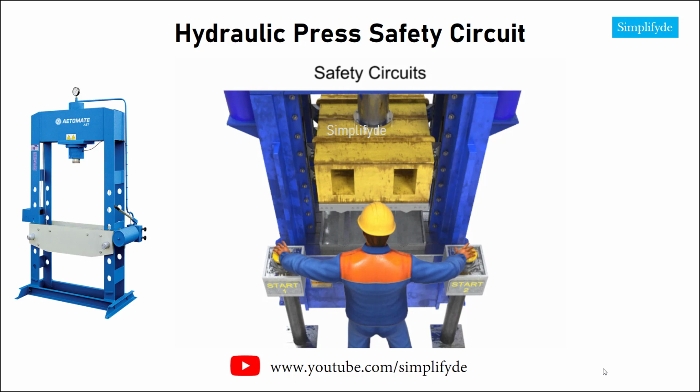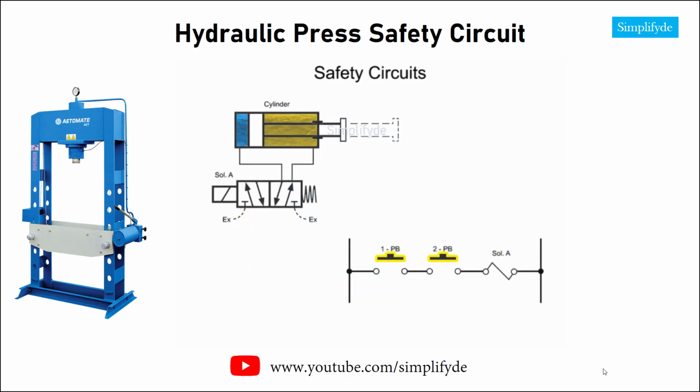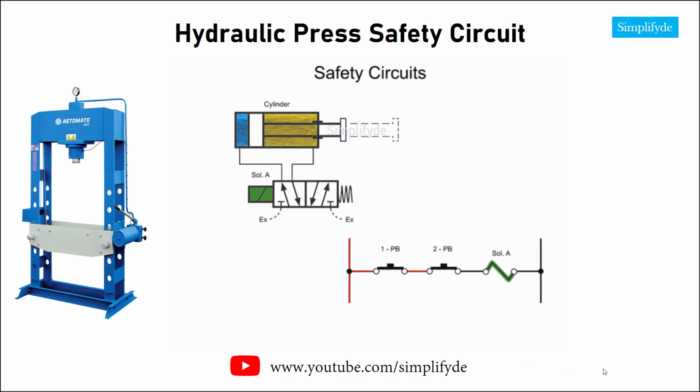Two-hand controls can also describe a machine that requires two separate operators, typically located on opposite sides of the machine. Both operators must be in place to allow the machine to start its cycle. For this type of machine, two-hand operation controls typically consist of two push buttons wired in series. This type of two-hand control is simple to install and is fairly safe if two operators are present with physically separate control panels. If only one button is depressed, the electrical connection is not made and the machine will not start. As shown in the circuit, only the actuation of both push buttons allows the solenoid to energize. The solenoid then shifts the valve to allow air into the cylinder, which produces the machine's stamping motion.